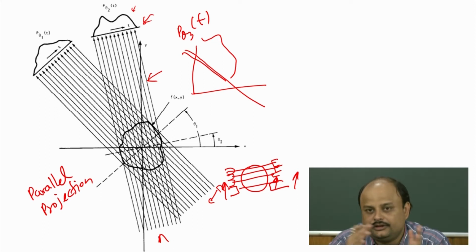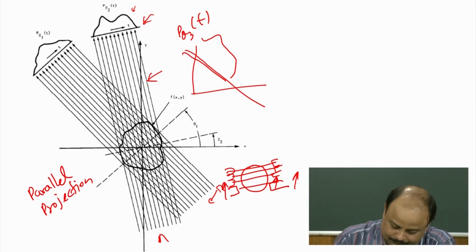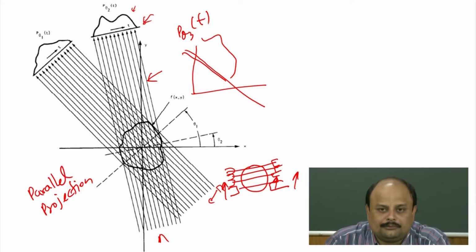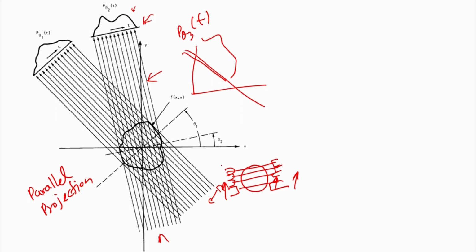Okay. So, that way the experimental time will be reduced. Just giving you the idea. Now, to overcome this, what is the problem in the parallel beam, and we will discuss again, that you will be required multiple sources. It means your overall radiation activity will increase. So, you require more and more safety gadgets. The safety requirement will be very stringent, and the safety gadget requirement will also be higher.